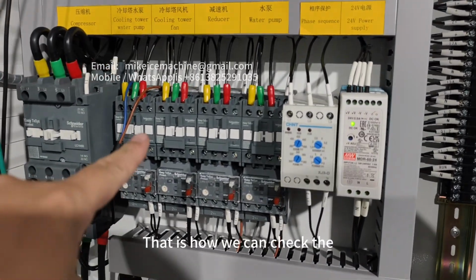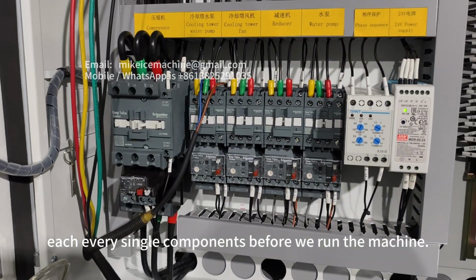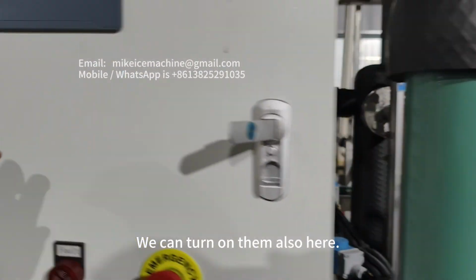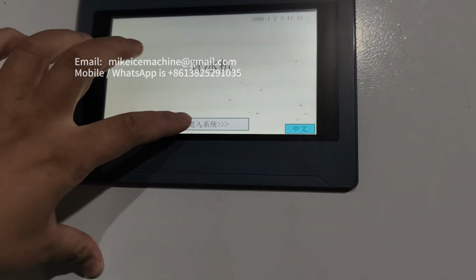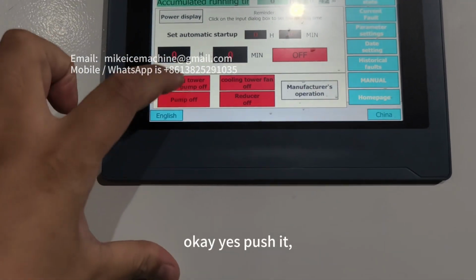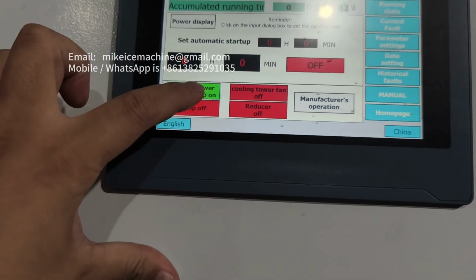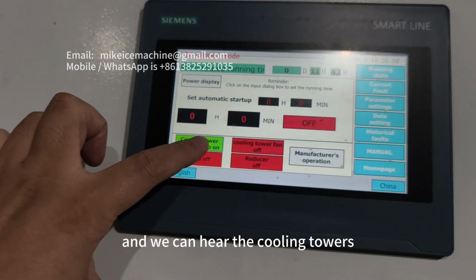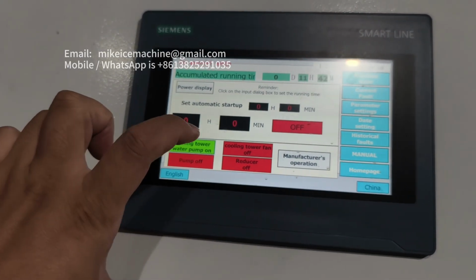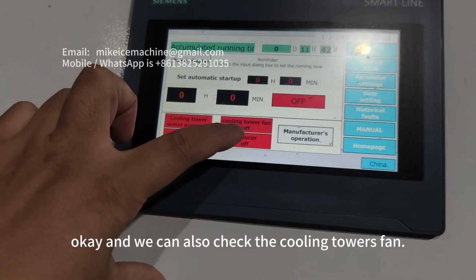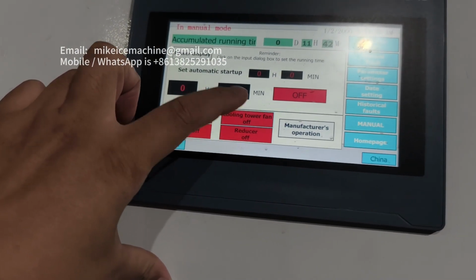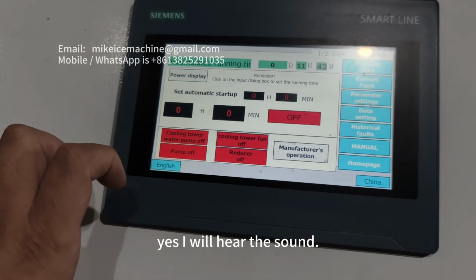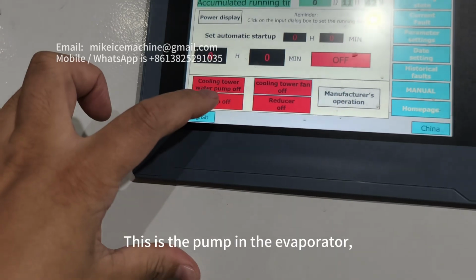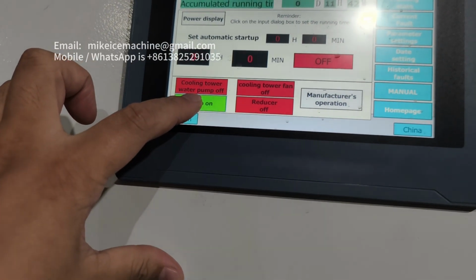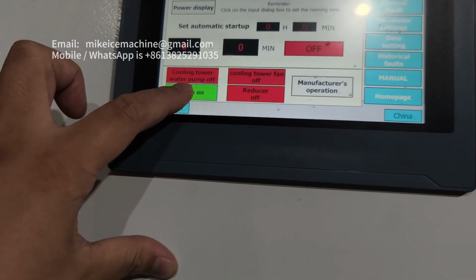that is how we can check every single component before we run the machine. We can turn them on also here. Okay, yes, push it, and we can hear the cooling tower's pump is working. Okay, and we can also check the cooling tower's fan. Yes, we hear the noise. This is the pump in the evaporator. Yes, did you hear the noise? Did you hear the sound of the pump working? Yes.